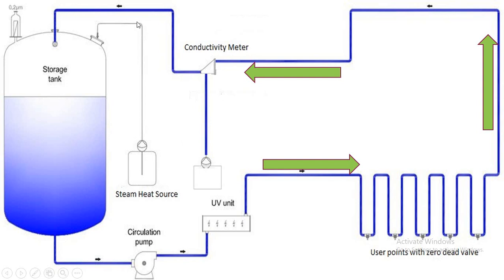There is a steam source line and a steam-jacketed tank. The circulation loop is maintained at 72 to 80 degrees Celsius. We can maintain this temperature to avoid microbial growth. There is also a breathing filter installed on the tank.